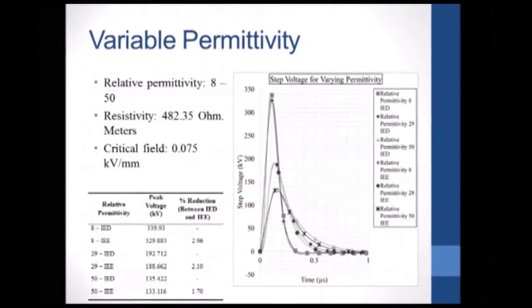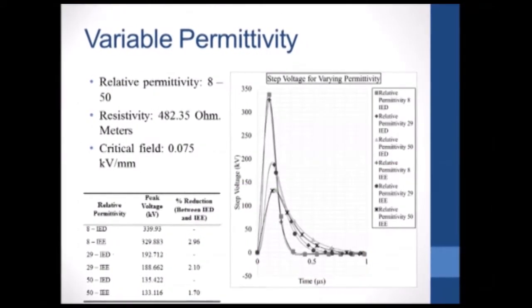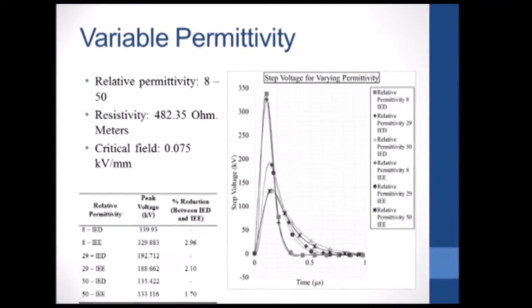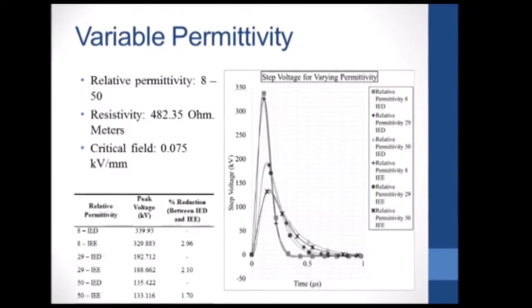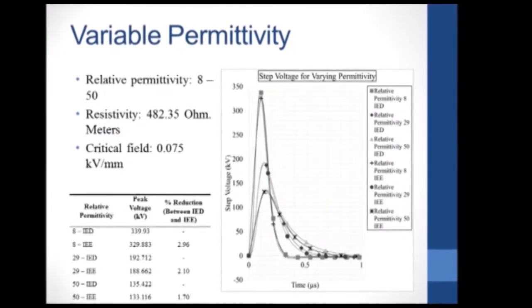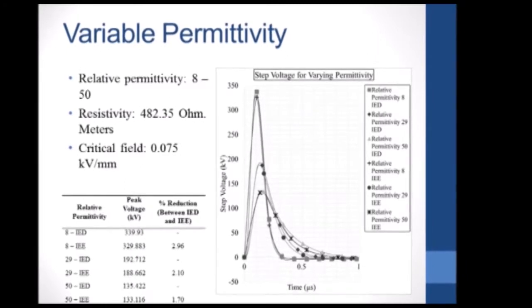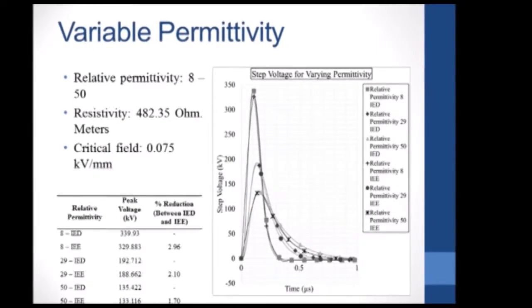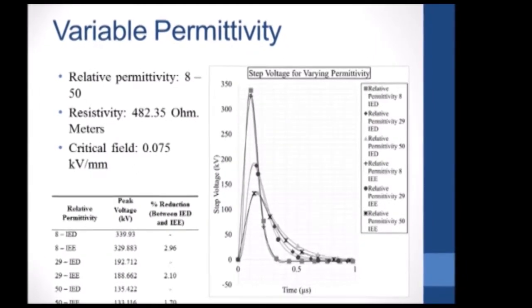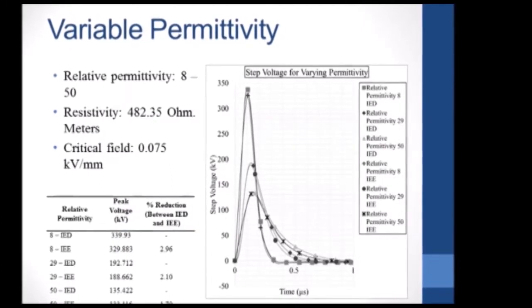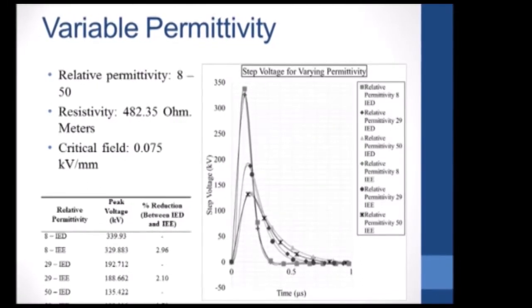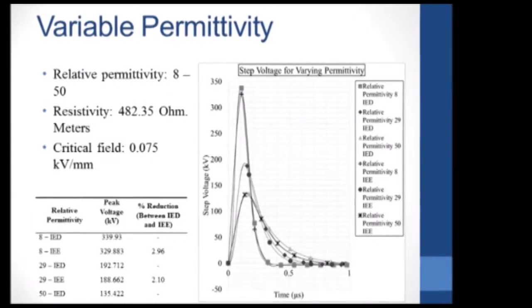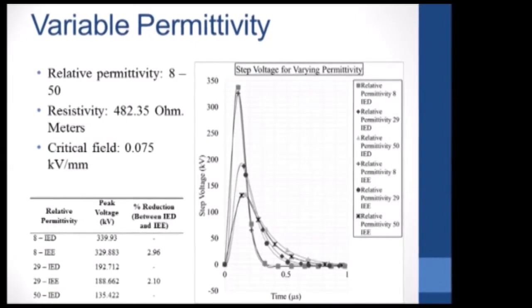For the variable permittivity, the permittivity was increased from 8 to 50 in three steps. The resistivity was fixed at 482.35 ohm meters, which is the average resistivity, and the critical field was set to 0.075 kV per mm, which is the worst case scenario for soil ionization onset. As can be seen from the table, the effect of soil ionization seems to decrease with increasing permittivity.